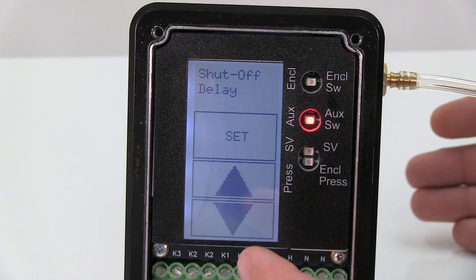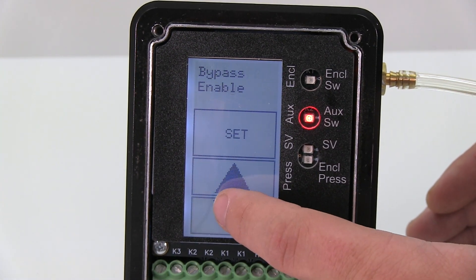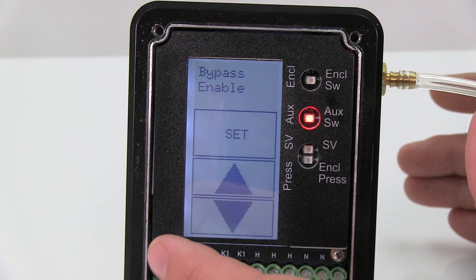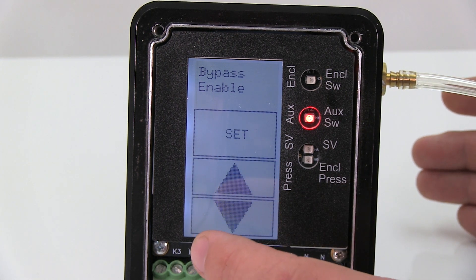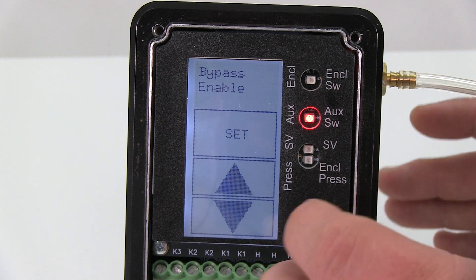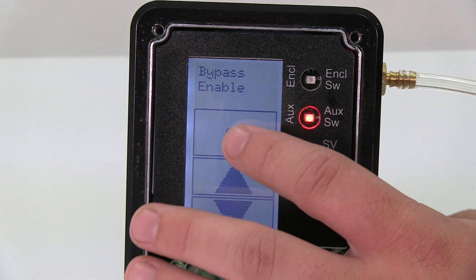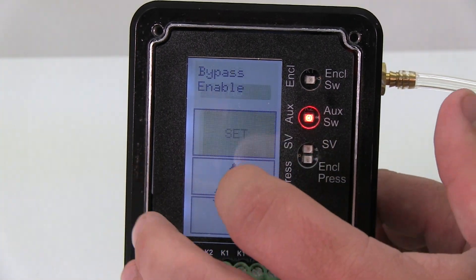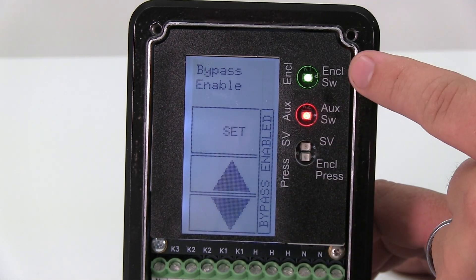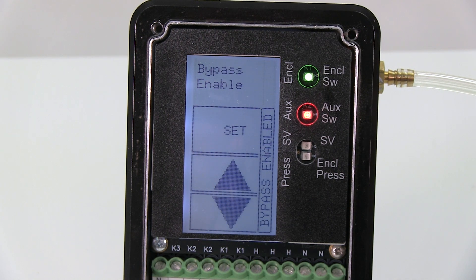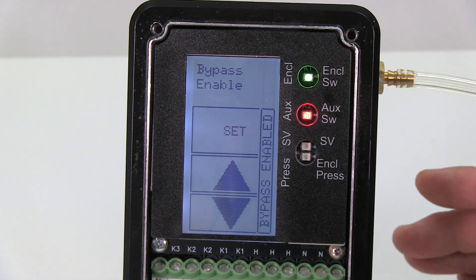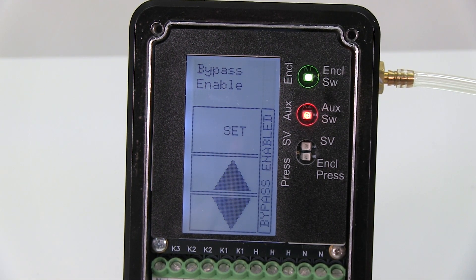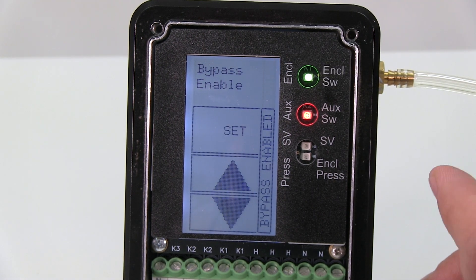Next menu item is bypass. This is just the bypass feature. So if you want to go out and do live maintenance on a machine but you don't want to shut down your process or set off alarms, you can take a gas sniffer out, check around the area, make sure there's no hazardous gas or dust, then put it in bypass mode. What that does is you can see that it'll close my enclosure power contact, so it keeps your enclosure energized so your process isn't going to shut down. You can also use this feature during commissioning if you don't have air to your system and you want to check to make sure the electric is working properly. You can enable the bypass which closes the enclosure contact, energizing your enclosure.